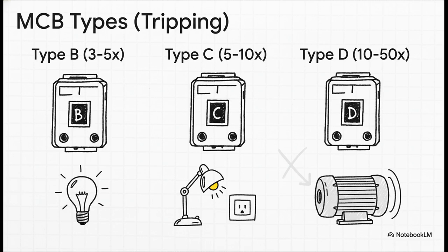And then, way down the line, for the final circuits, the ones that are actually feeding the lights and the outlets, we have miniature circuit breakers, or MCBs. The different types you see here, B, C, and D, are really all about handling the initial surge of current when something turns on. You would never use a sensitive type B on a huge motor, for instance, because that startup surge would just trip it every single time. You have to match the breaker to the load.